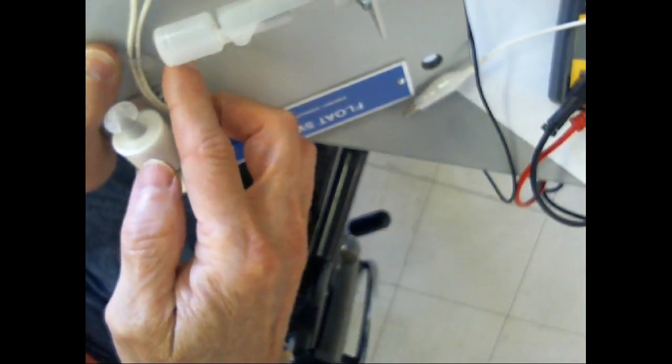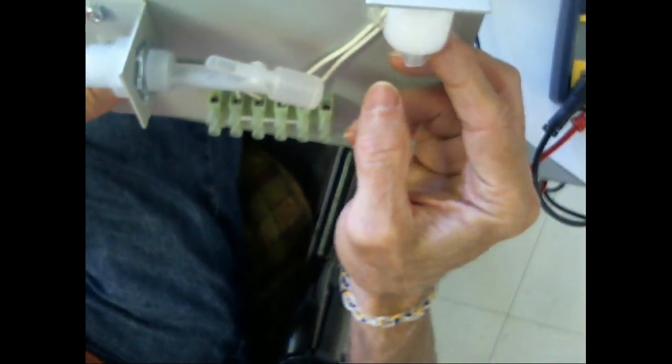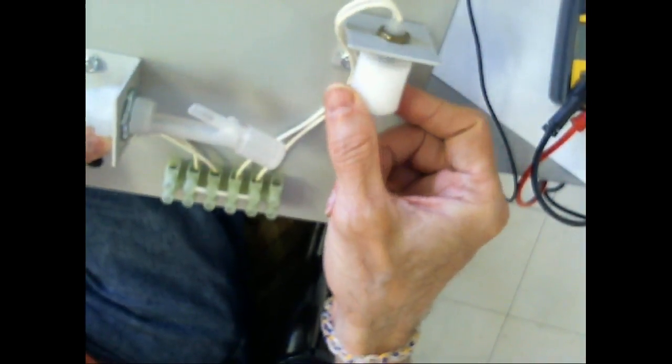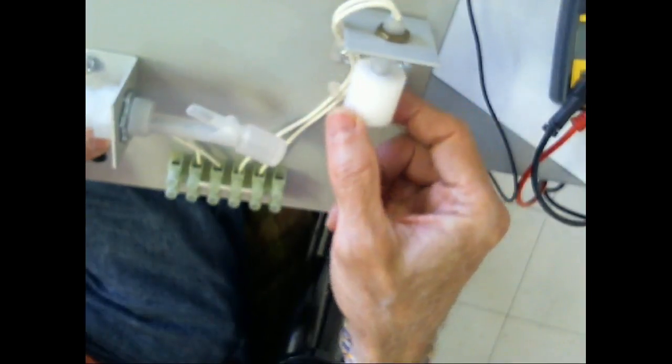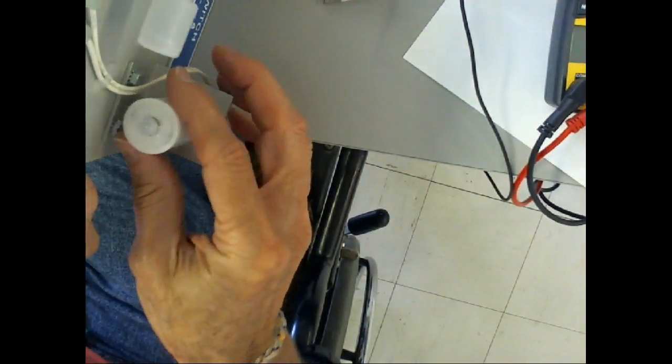So a charging system means we're looking for the level to go up, right? And then we turn it around. This could be used for a discharge system. Now, this could be used for charging either way. It depends on what you look at, whether the contact is open or closed. This works on a reed switch also. So this has a magnet in this thing, and when it moves up and down, it makes the reed switch, right? And we can mount this different ways too.